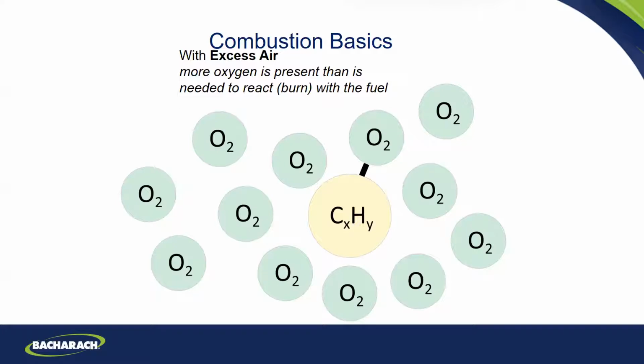Not only do we have a big bubble of oxygen, we've got a bubble 4 to 5 times bigger of nitrogen that we're heating up and sending outside. So we basically want to add enough oxygen to bond the fuel molecules, but not so much that we're lowering our efficiency. That's what combustion efficiency is all about.